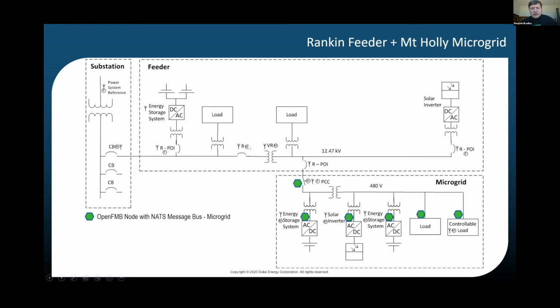We have reclosers, which is just a fancy kind of switch that's in the middle. So if there's faults down here, this recloser can open up and power can still run up here. We have reclosers in front of the microgrid as a protection device. So if the feeder sees something going wrong with the microgrid that it shouldn't be doing, this recloser can open and kind of island the microgrid away from the feeder.